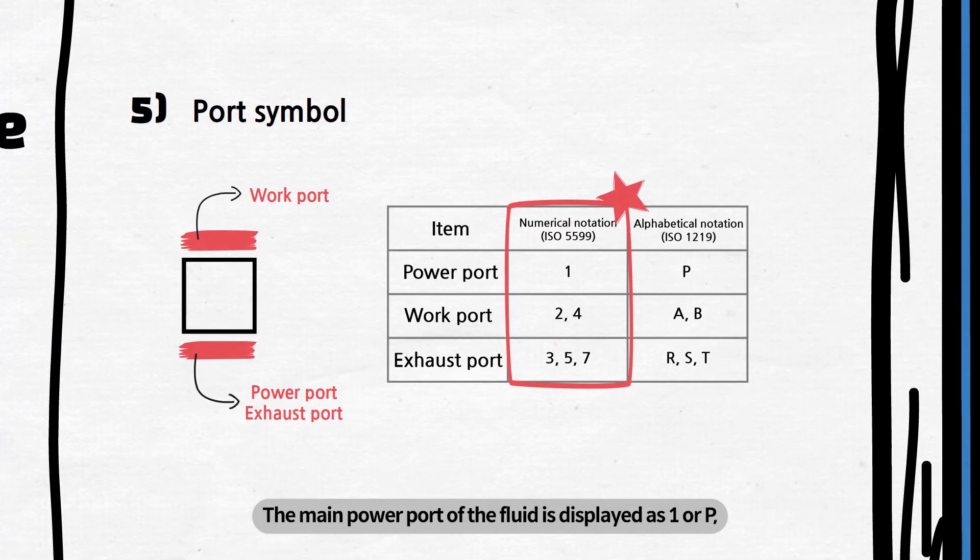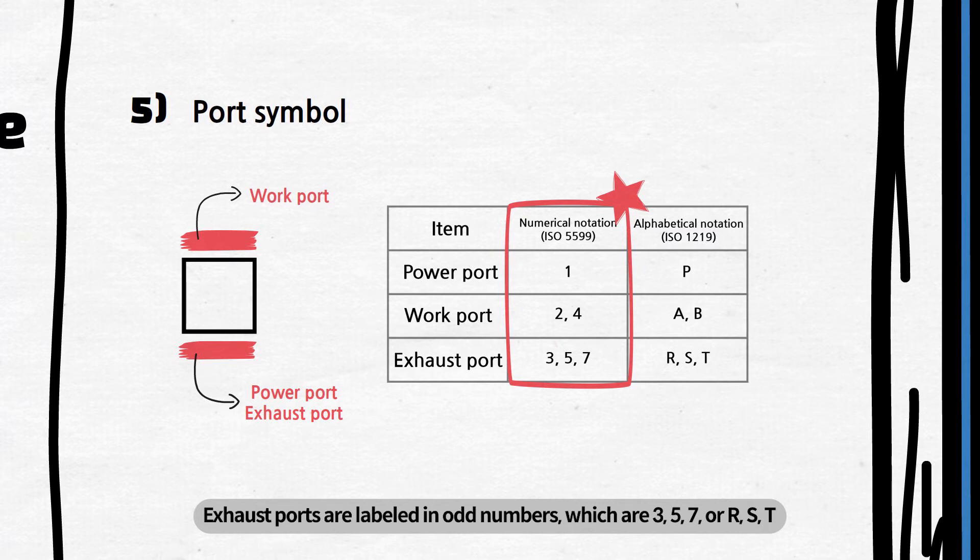The main power port of the fluid is displayed as 1 or P, while the working port shall be in an even number, which is 2, 4, or A, B. Exhaust ports are labeled in odd numbers, which are 3, 5, 7, or R, S, T.